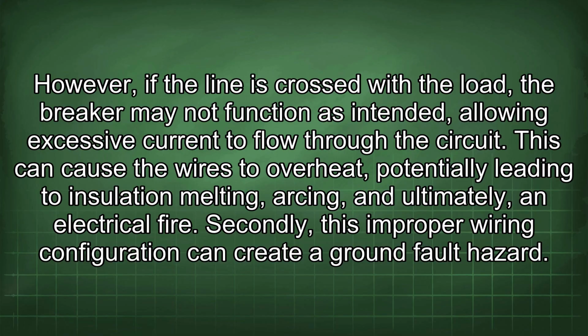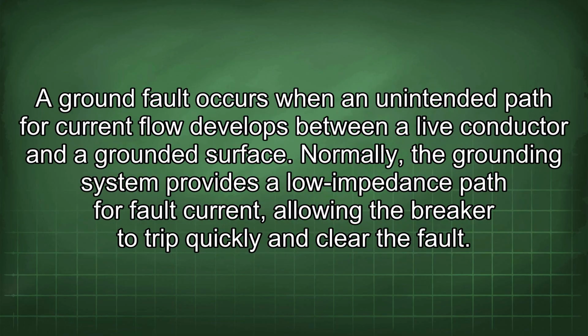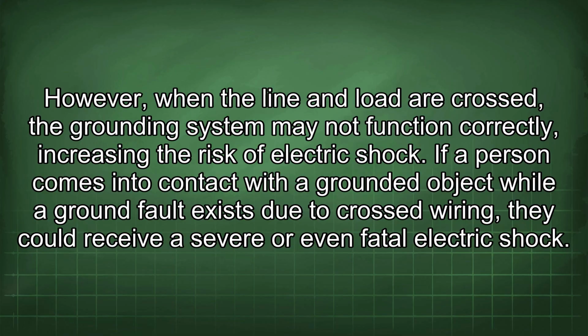Secondly, this improper wiring configuration can create a ground fault hazard. A ground fault occurs when an unintended path for current flow develops between a live conductor and a grounded surface. Normally, the grounding system provides a low impedance path for fault current, allowing the breaker to trip quickly and clear the fault. However, when the line and load are crossed, the grounding system may not function correctly, increasing the risk of electric shock. If a person comes into contact with a grounded object while a ground fault exists due to cross wiring, they could receive a severe or even fatal electric shock.